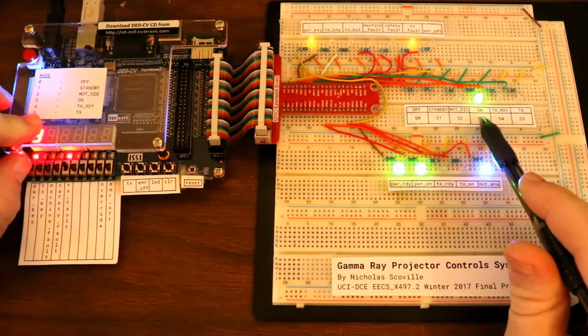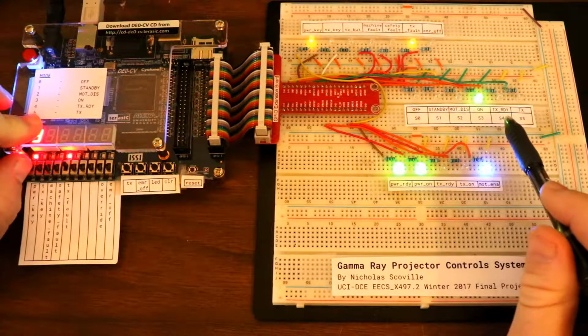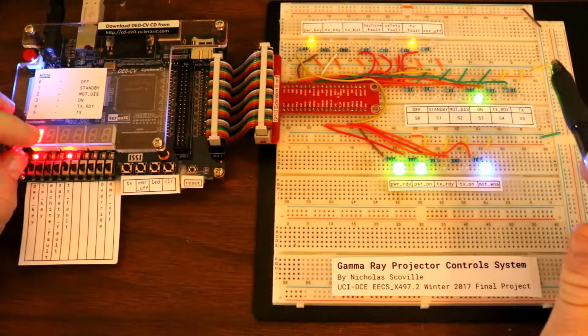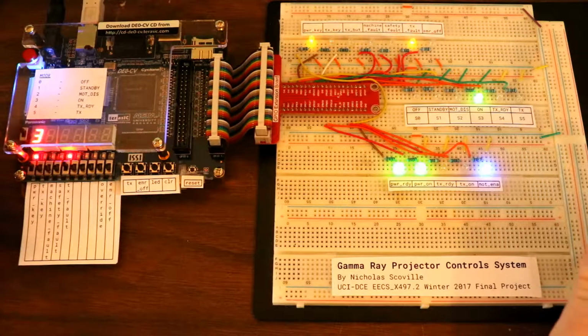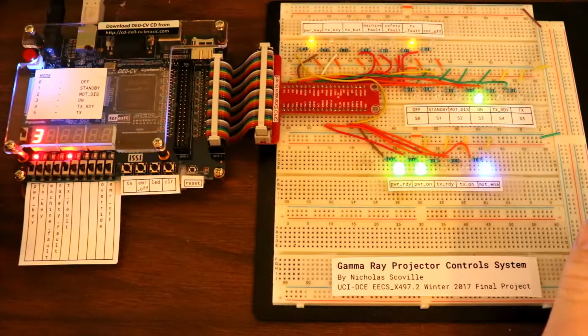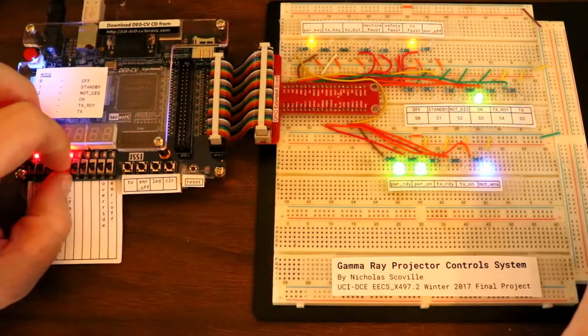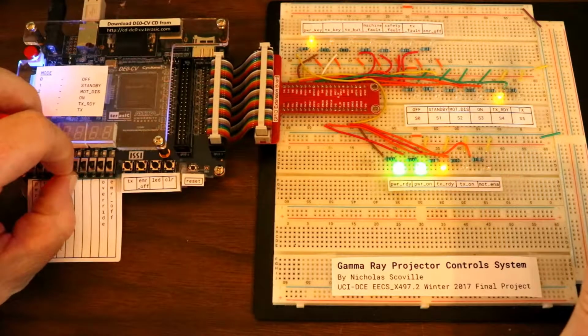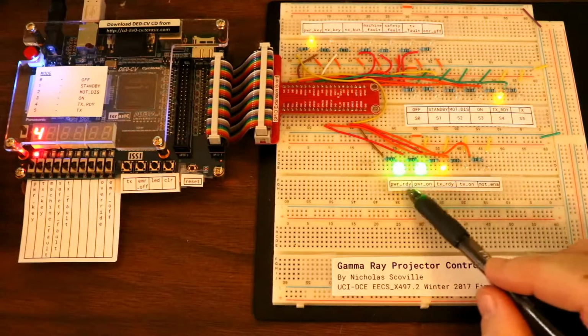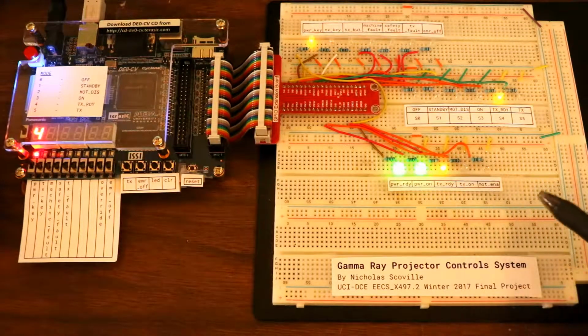So now that I've entered the on state, if I wanted to go to the transmit ready state, I would need to remove this transmit fault. And the way that you would normally remove the transmit fault would be to correctly prepare the machine to mode up by entering values on a time limit and other things like that to prepare the machine. So let's say that we've done that. Now the machine enters the transmit ready state, and over here we have a transmit ready signal.